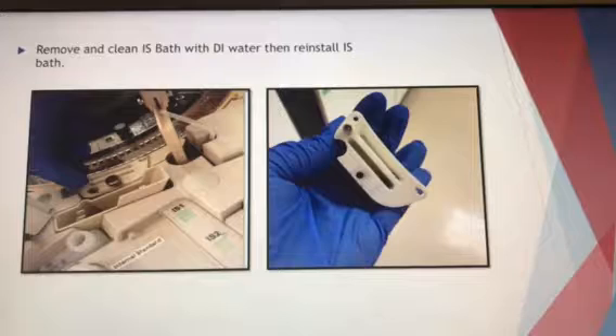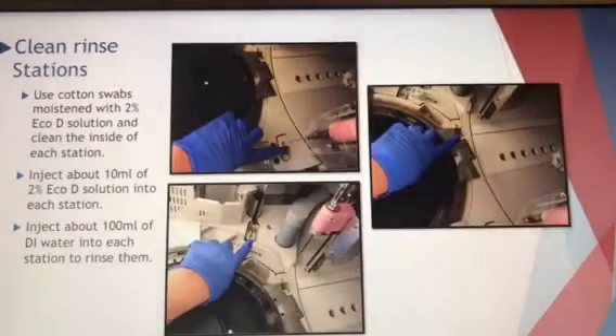Just take a cotton tip applicator, moisten it with DI water, and just get inside of those creases and clean it really well. And then put it back, and then screw the little caps back on. And you're done with that. And then the next thing you're going to do is clean your rinse stations. In each of those pictures, there are 3 rinse stations, and there are 3 pictures to show you where each of them are. And you're going to use your cotton tip applicator, and you're going to moisten it with your 2% Eco D solution, and go ahead and clean inside each of those.